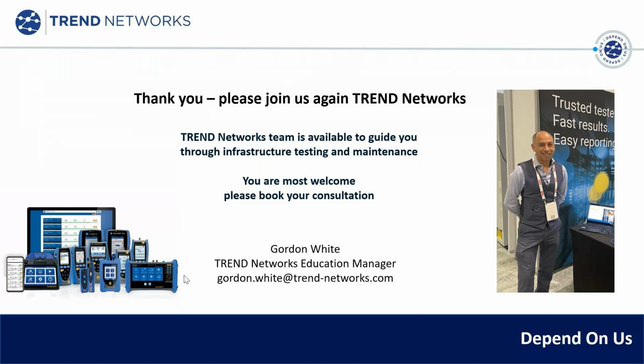So you have the trilogy. That is the best and ultimate infrastructure test. I hope that helps, because you can do proof of performance for commissioning. If you have a critical service, such as a communication system that must not go down, SignalTek 10G could do a 72-hour test across that link. I hope that helps. Thank you again.